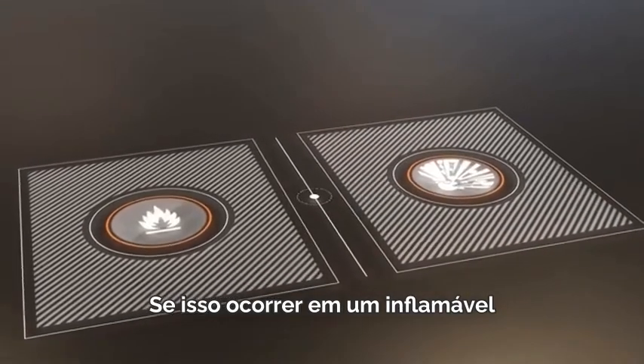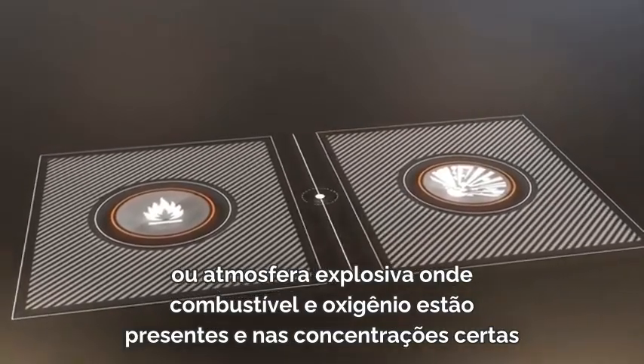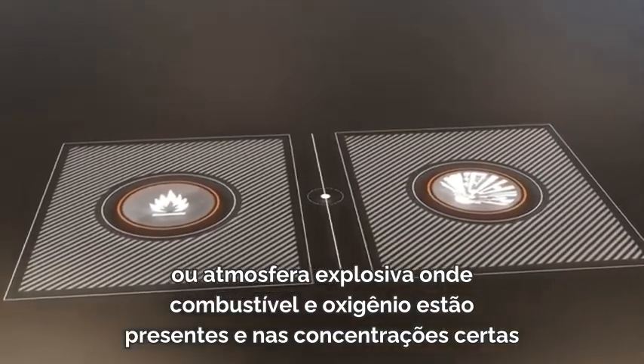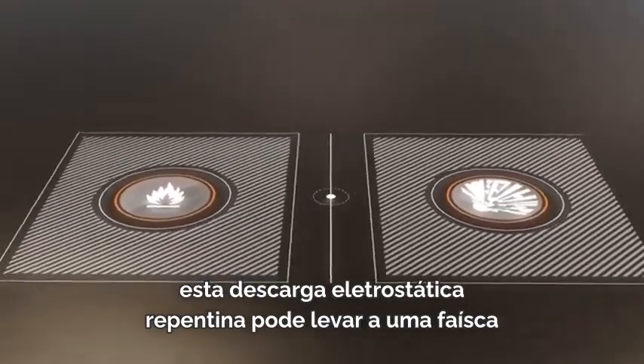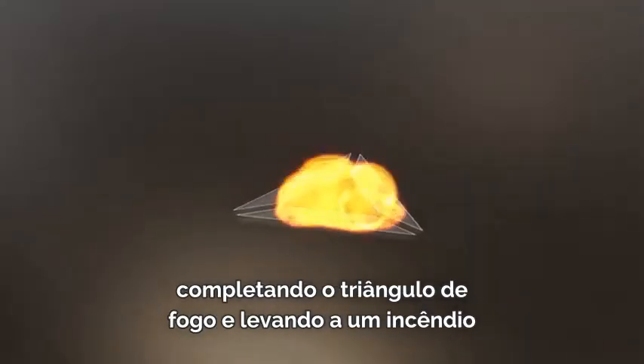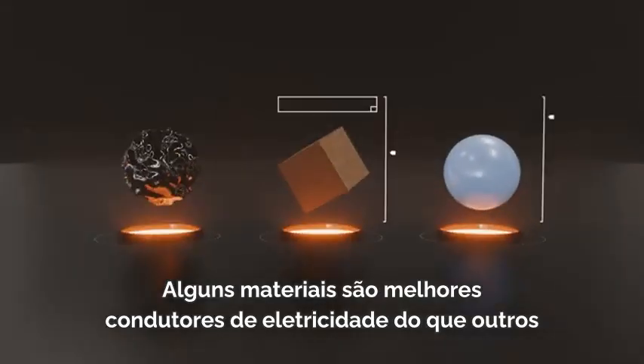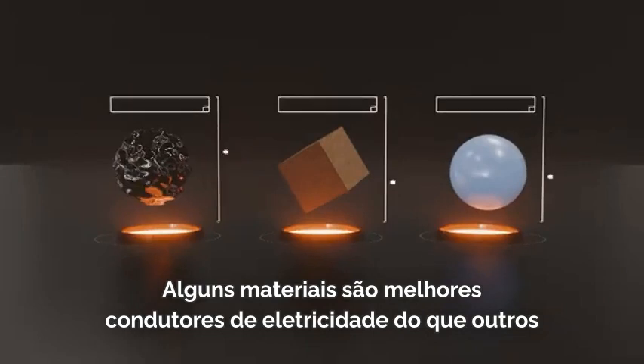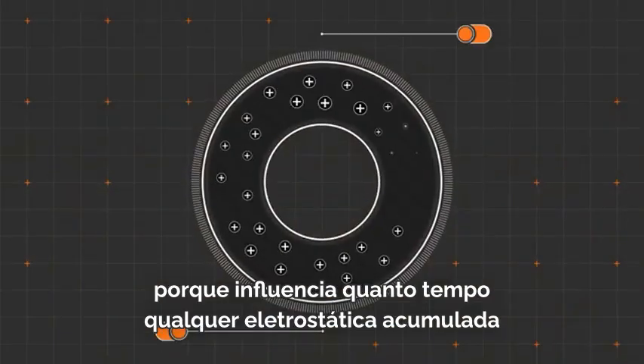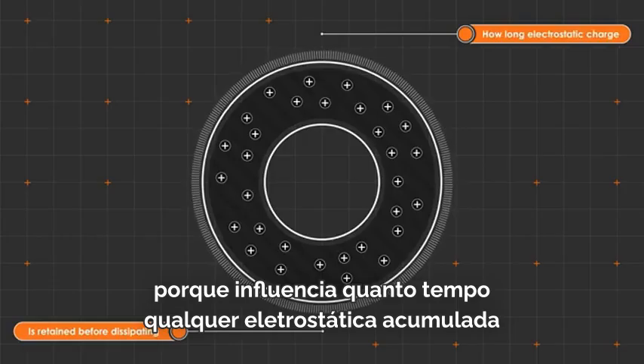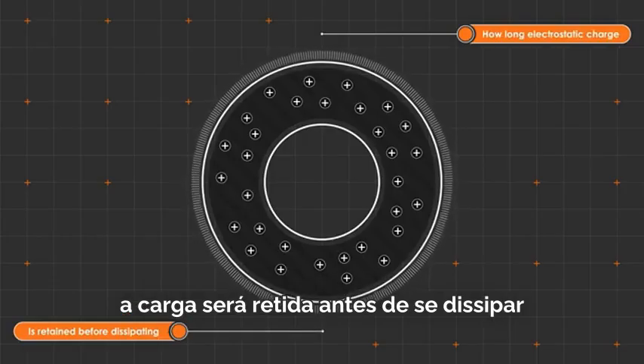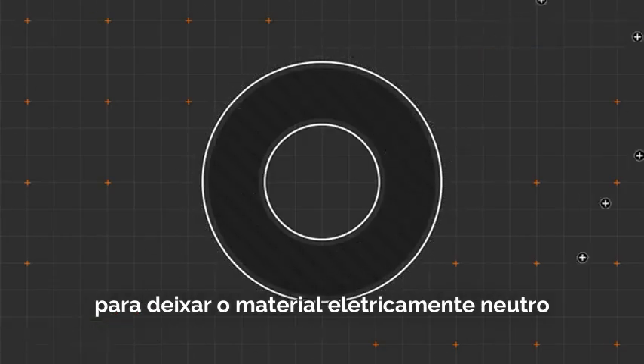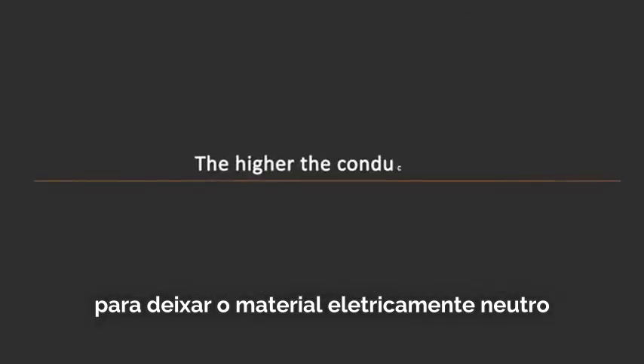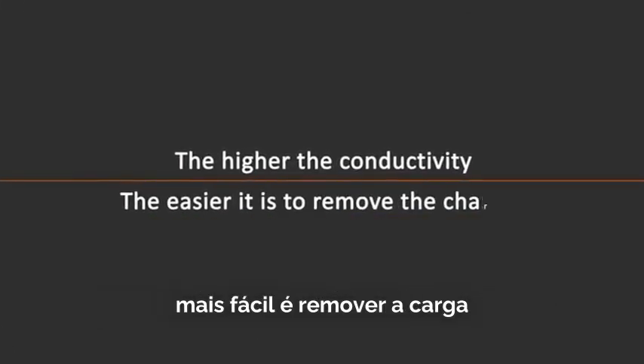Should this occur in a flammable or explosive atmosphere, where fuel and oxygen are present and in the right concentrations, this sudden electrostatic discharge can lead to a spark, completing the fire triangle and leading to a fire, or even worse. Some materials are better conductors of electricity than others. Conductivity is important because it influences how long any accumulated electrostatic charge will be retained before it dissipates to leave the material electrically neutral. The higher the conductivity, the easier it is to remove the charge.